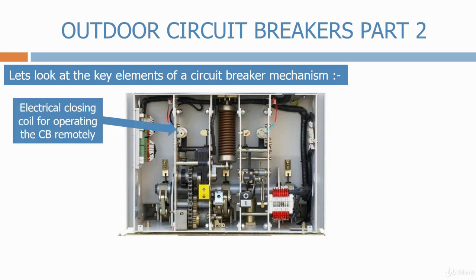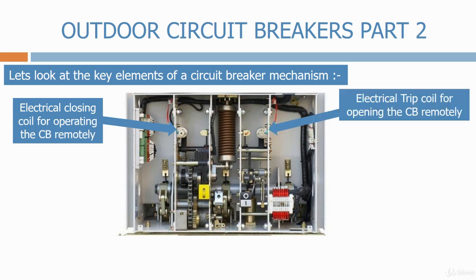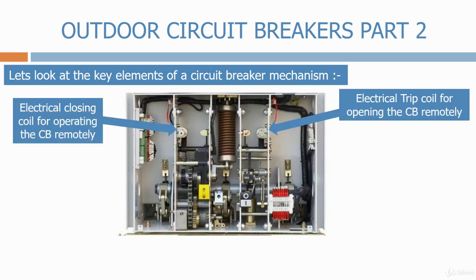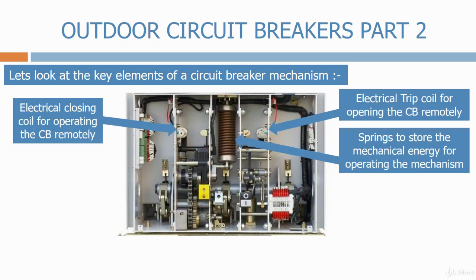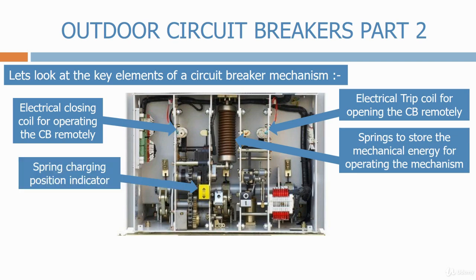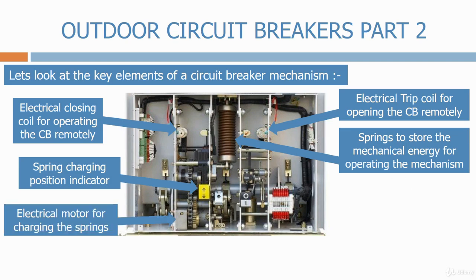First, we have the electrical closing coil for operating the CB remotely. We then have the electrical trip coil for opening the CB remotely. These close and trip coils are basically heavy-duty solenoids, which mechanically force the mechanism to operate. We have the springs to store the mechanical energy for operating the mechanism. We have the spring charging position indicator, which shows whether the springs are charged or not. We have the electrical motor for charging the springs.